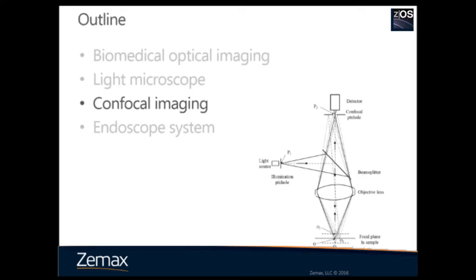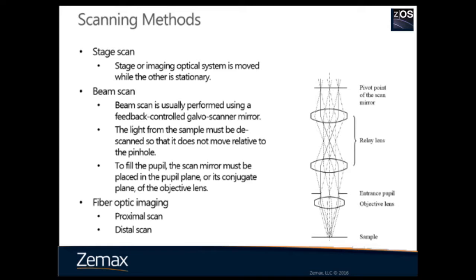The next topic is confocal imaging. Compared to a conventional microscope, the difference is there is a pinhole in front of the detector. This pinhole rejects light from out-of-focus planes. For better performance, a pinhole is also needed in the illumination path, but if you use a laser, that is not necessary. Because there is a pinhole in front of the detector, confocal imaging is a point imaging system. You need a scanning mechanism to create a 2D or 3D image. The simplest scanning method is stage scan. The most commonly used system is a beam scan, using a scanner to scan the focus across the sample. Fiber optic scanning is also an option, especially in endoscopes.